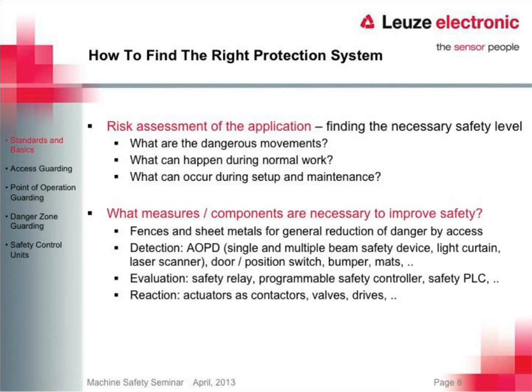When we're talking about safety on a machine, the first thing we have to do is determine what the right protection system is for the application. The easiest way to do this is with a risk assessment, which helps us find the necessary safety level and figure out which hardware components are best suited. We need to think about what the dangerous movements of the machine are — whether it's a press brake, a robot cell, or something else. We also need to consider what can happen during normal operations like loading, unloading, and cycling, but also during setup and maintenance, where we may have a bypass switch to disable some safety functions.